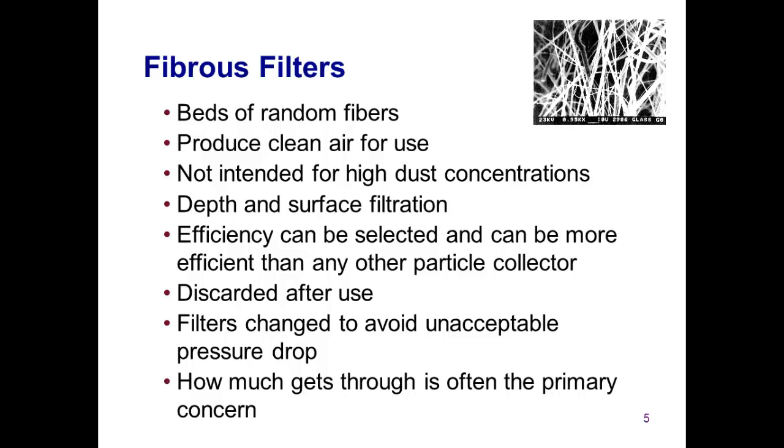By designing the filter appropriately, you can achieve virtually any efficiency desired. Therefore, fibrous filters can be more efficient than any other particle collector. They are generally discarded after use because the particles cannot be removed readily by cleaning. When the pressure drop gets too high, the filters are changed to avoid that unacceptable pressure drop. Frequently, how much of the incoming aerosol gets through is the primary concern. These types of filters are used commonly for ventilation purposes, including ventilation for swine facilities.